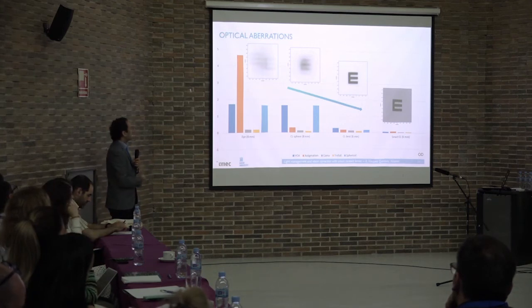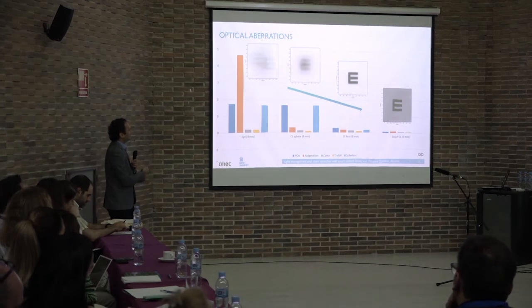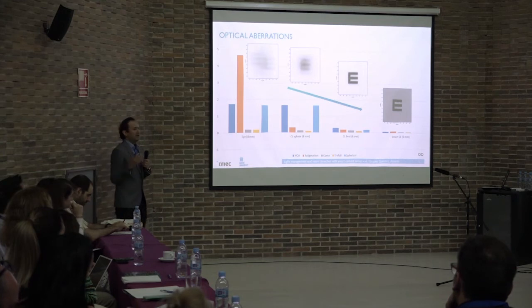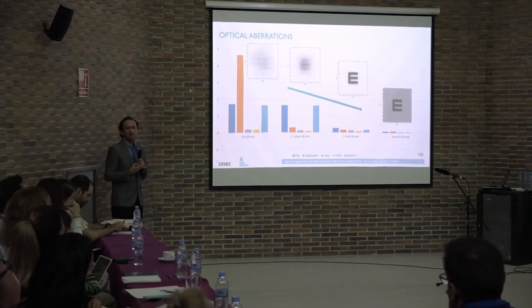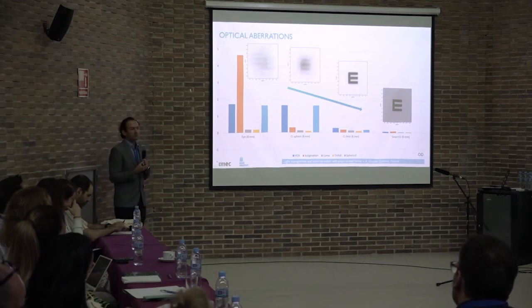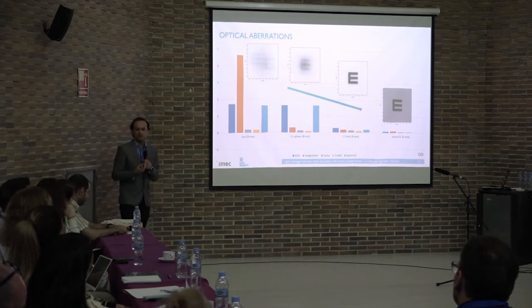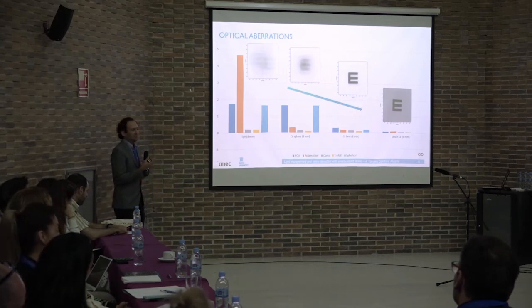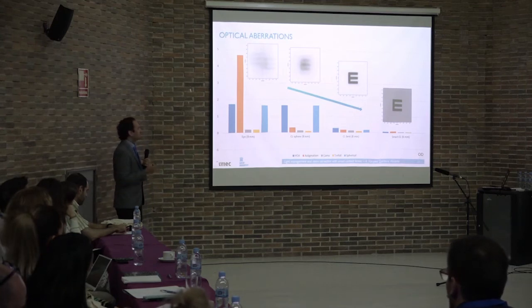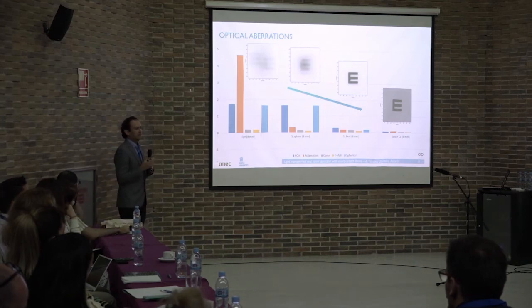But then if we start to design contact lenses with a correct spherical correction of the smart contact lens, then we actually saw how we could reduce and remove the optical aberrations, just because we were removing the area where the light was going through the cornea. So then we have three effects. We have less light, which is good. We have the pinhole effect, which increases the depth of field, but also we remove optical aberrations from the large area of the cornea.